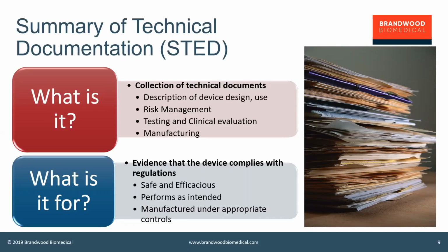So if anything comes out of your STED, you should be able to make the statement that you have met the safety and efficacy required for this device to be effective in what it's trying to do. That it's performing as it intended, and again, that it's manufactured under appropriate control so that there's no question that, as you manufacture this on a regular basis, it will be the same device in a controlled manner.